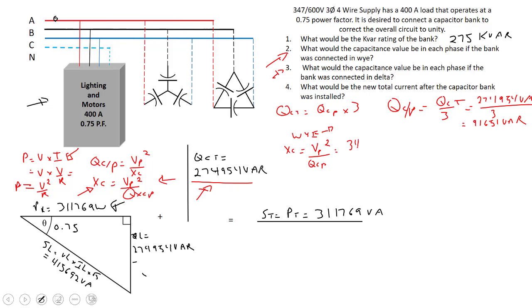346.4 volts is our phase voltage. We're going to square that value and divide by our 91,651 VAR. That's going to come to about 1.309 ohms.